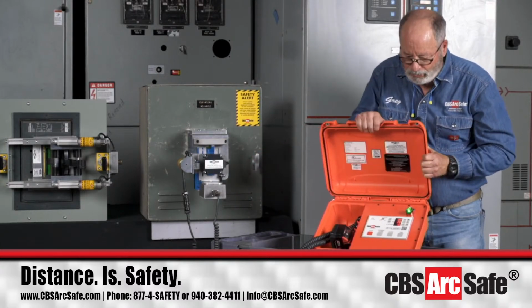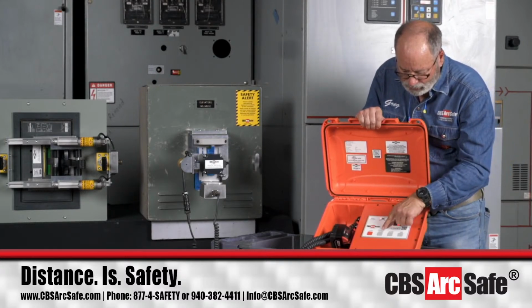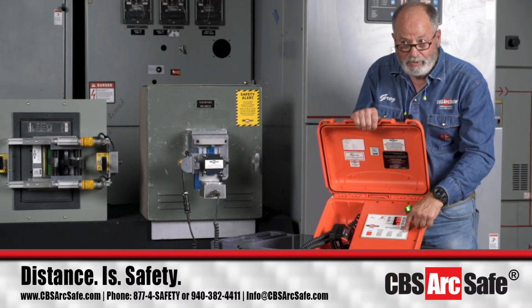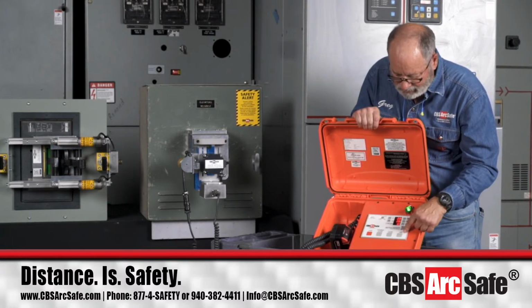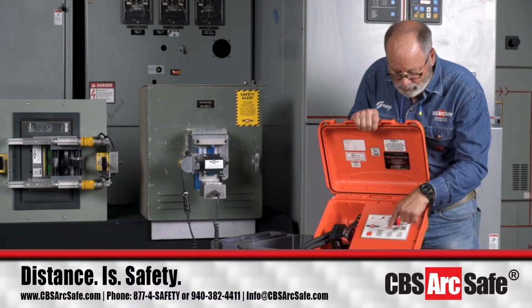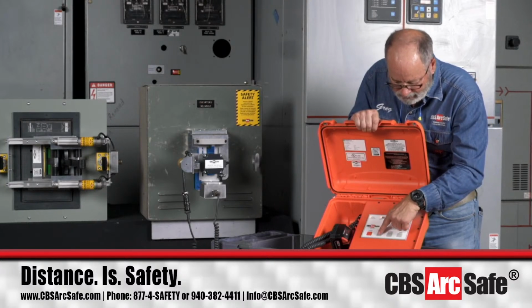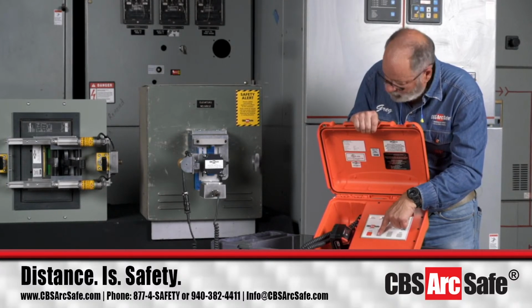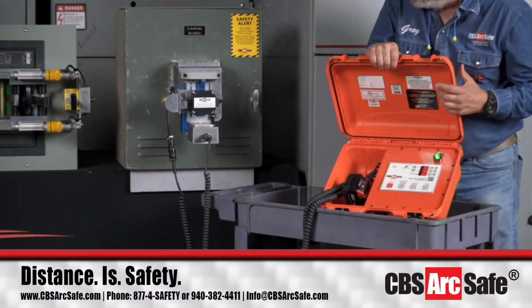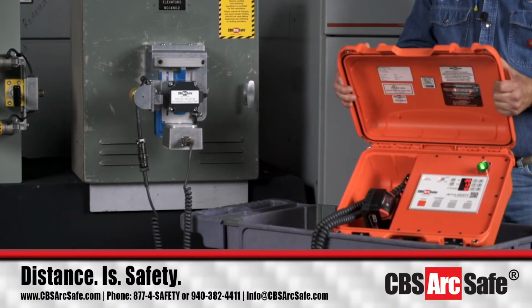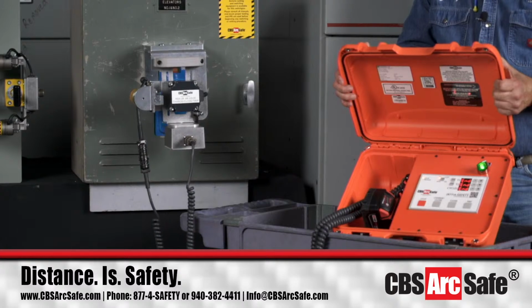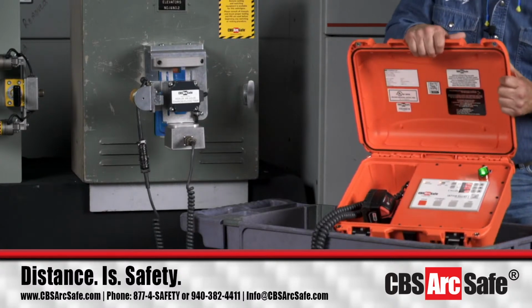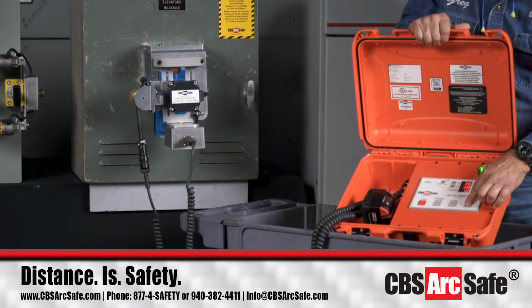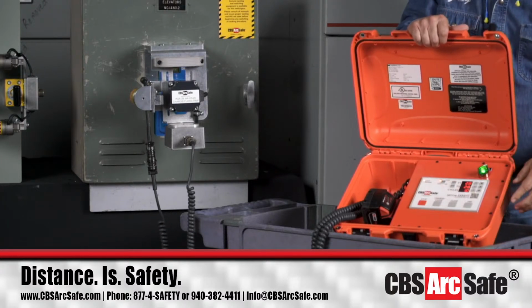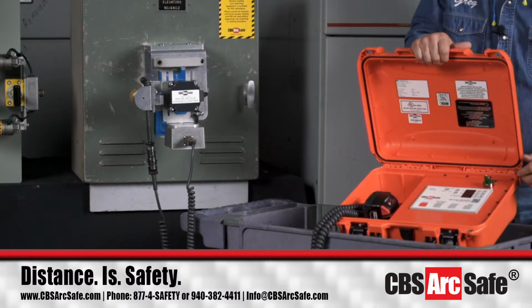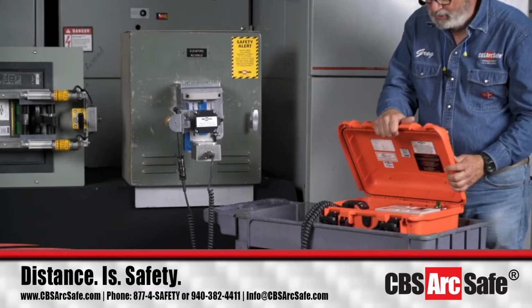The only two buttons we're going to use with this actuator are actually charge close and trip. If it was a DS breaker, we'd charge it with this, close it with this, and then trip it with this. But this one, and something like a K-line, you just push the button once and it goes into motion, and it comes back down now, and the breaker's closed. Now we want to trip it, we just push the button once, and now the breaker's tripped. That's the ease of operation of this system.